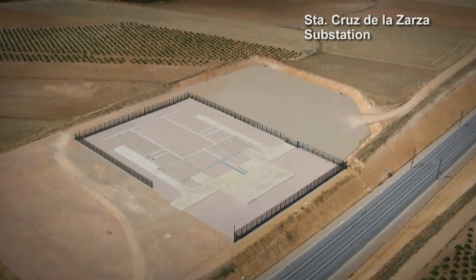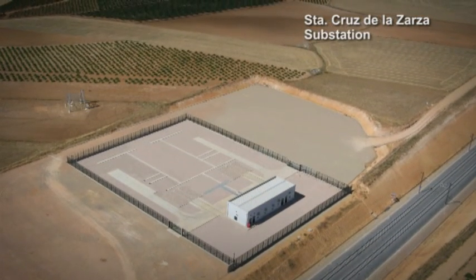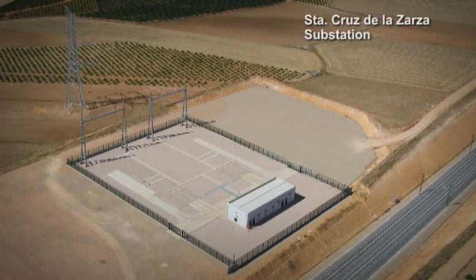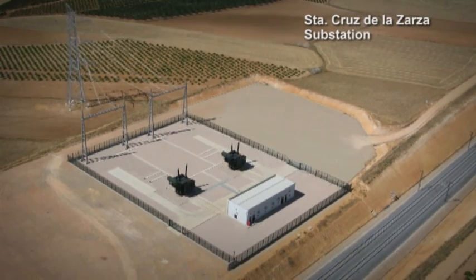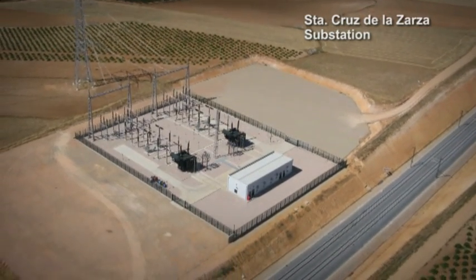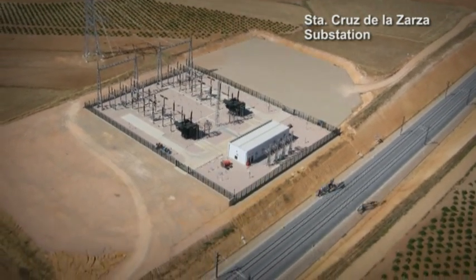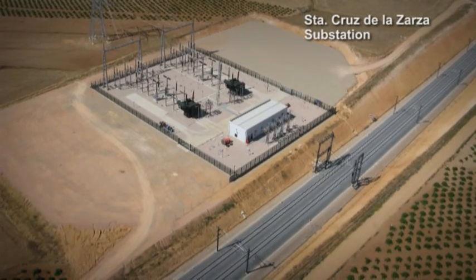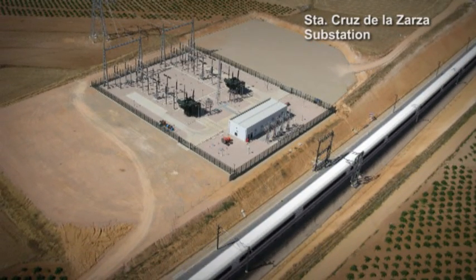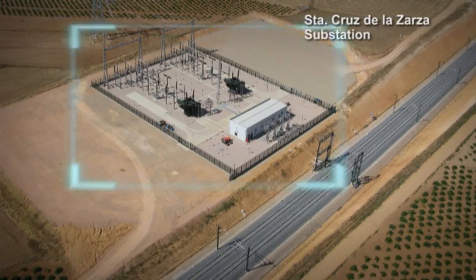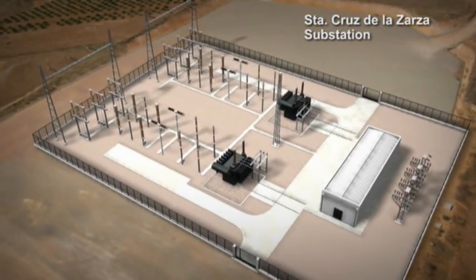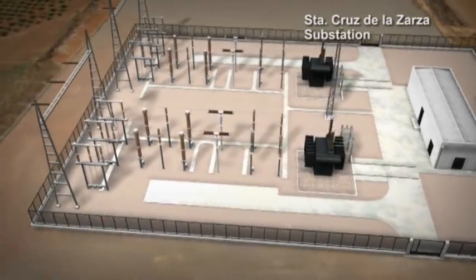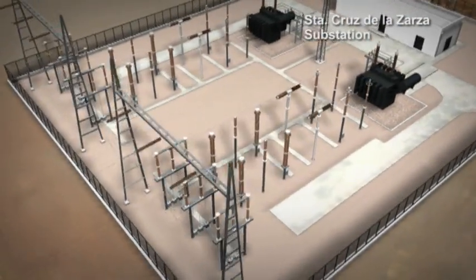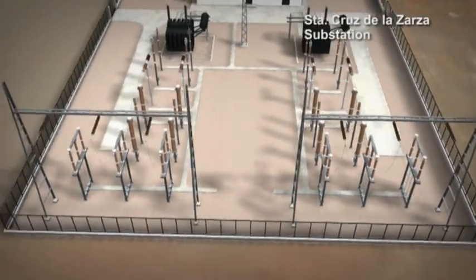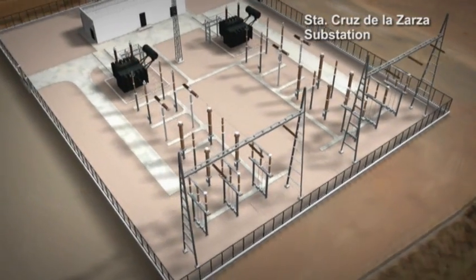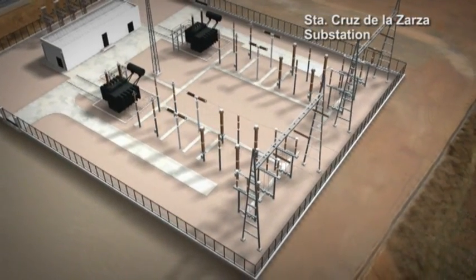After the relevant environmental and geotechnical reports and archaeological supervision, each of the electrical traction substations will be built on a leveled, compacted platform. The high-tension equipment and the control building will be located on these platforms. Each substation will connect to the Spanish main power grid via 400 kilovolt high-voltage lines. 2 60 megavolt ampere transformers will be used to reduce the 400 kilovolts to a voltage of 2 times 25 kilovolts.